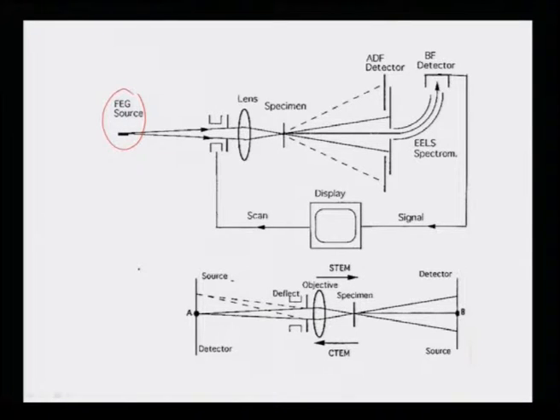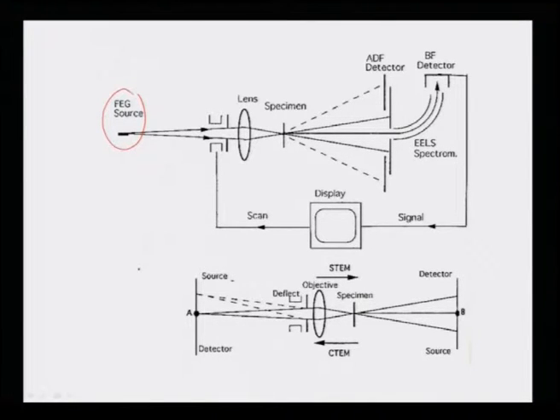A 1 nm FEG beam has a current of about 0.5 nanoamps. That is why with a FEG, bright-field and dark-field images can be easily recorded within a few seconds, or even at TV scan rate — which is what we want: the beam scanning the sample and the image displayed at the same scan rate. To achieve TV scan rate, you need sufficient beam intensity.